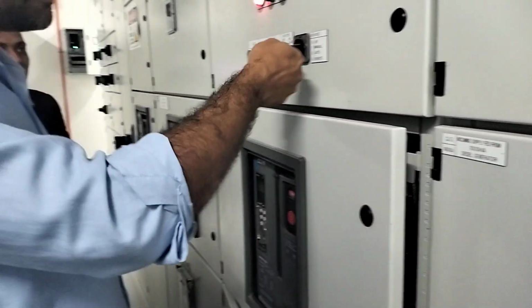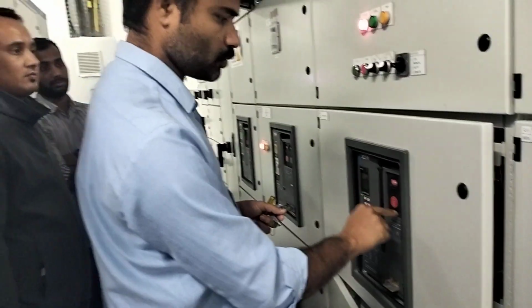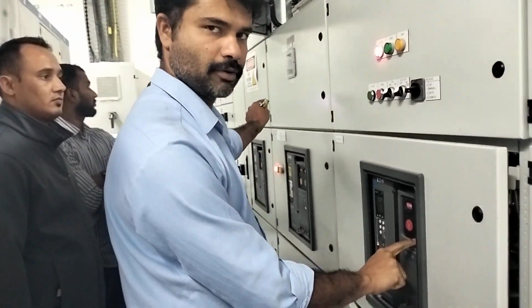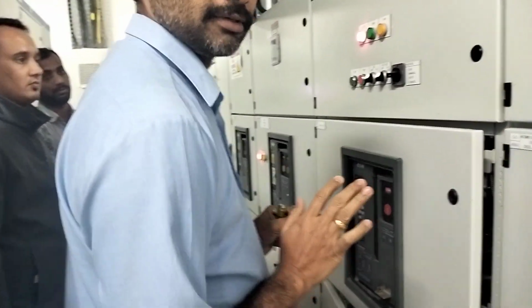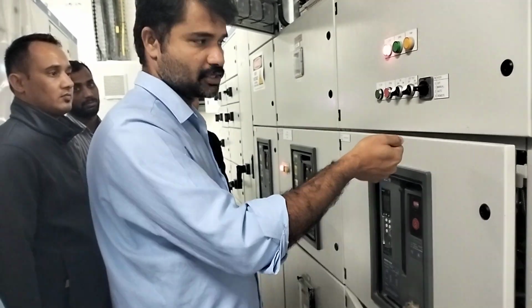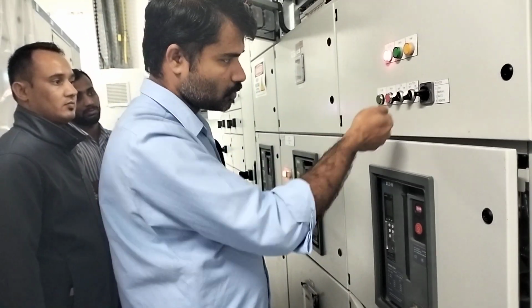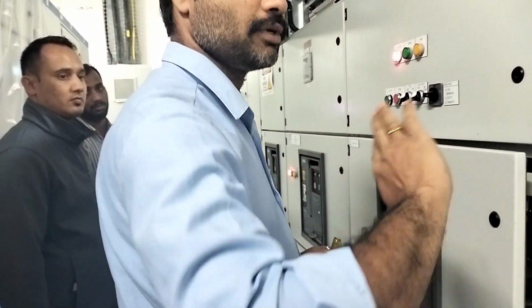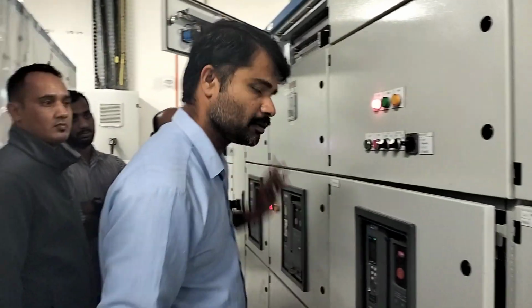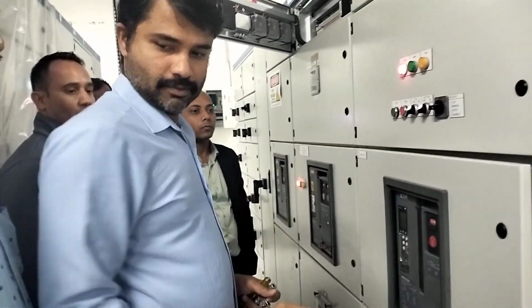If you are in manual, do one thing: put it in manual, run the generator, and open only the coupler. Let it run, no problem. You can close this one. Same thing in auto condition. If it is on load, keep the on-load test, this will open and this will close. So this is feeding the emergency power, and this is feeding the normal power. The generator will feed this, because this will trip. Trip means cut from this.